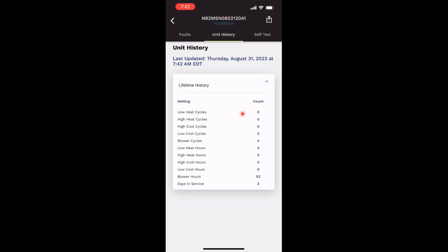This is where I have low heat cycles. It tells you how many counts. We've had 4 counts on the blower cycles, and that particular motor that I demo has had 92 hours of life on that blower motor, and showing 3 days of service. So this will tell you the lifetime history of the furnace, the unit, and you'll be able to read your fault codes. This is something you can't see when you're doing it manually. You don't see any of this.